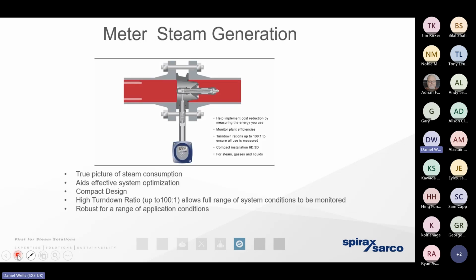So, bearing that in mind, the next thing that we want to look at is ensuring that we've got a meter for each individual steam boiler, or at the very least 1 meter per boiler house, because it's only by metering the mass of steam that is being produced that we can really say with any real confidence that we understand what our cost of steam is. And then if we're metering the steam that is leaving the boiler house, and we're metering the steam as it arrives at each individual building or heat exchanger, well, that way we can understand how much steam is going missing in the middle. And that could be down to having excessively wet steam that's condensing out in the pipes, or it could be down to the fact that we've got failed steam traps.